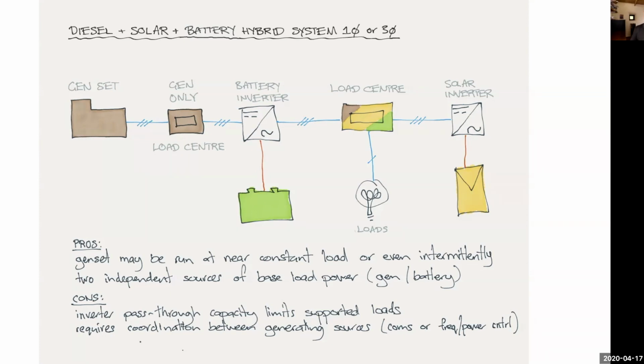But if you're doing quite a big installation, you have to consider what is the maximum pass-through capability for when the generator is running and the loads are drawing very high current. Some battery inverters allow external contactors to be installed as well, so the limit's almost the sky. On my system here, I think I've got a 250 amp contactor on the output, so I could run a ridiculously large load for what is effectively a small microgrid of 7 homes.